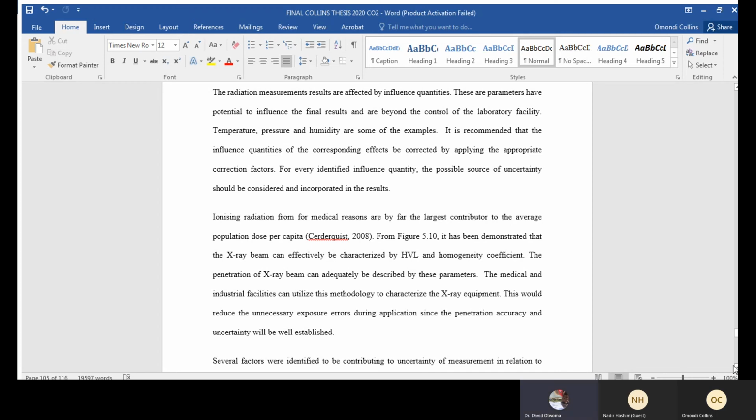And then I hope that you also have a survey meter which is similar to those, which is more of a reference standard, so that if there are any unexpected changes in the exposure rates, they are identified. But if you do not have one, this is again a time when you call for Kenya Bureau to acquire one, because in your experience with, for example, hospitals, you know what type of survey meter they use. So it would be good to have one similar survey meter, but yours is a reference standard.